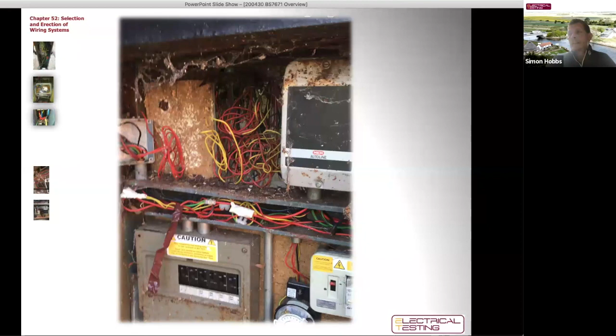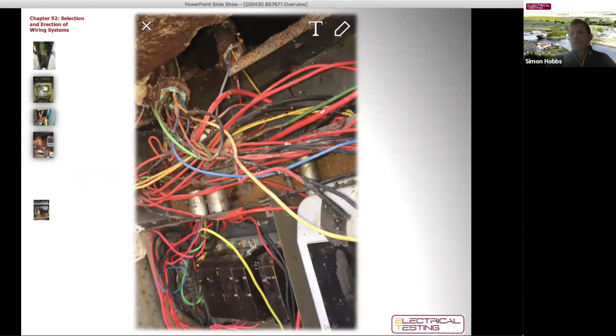Then progressively getting worse, we've got cables that are not correctly run in routes, it doesn't look particularly neat and tidy, and doesn't meet very many requirements of the regulations. Again, a horrendous installation that doesn't meet a huge number of the requirements of the regulations. And finally, this particular slide, this was an installation in a switch room that we entered. I entered personally as well with my engineering manager, and we opened the door and the cover, this is as we found it. So the cover is missing. We've got live terminals, bare live terminals here. You know, it's an absolute death trap. So all part of chapter 52, amongst other regulations as well.